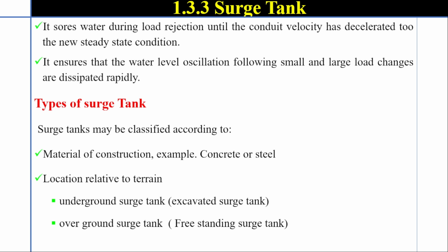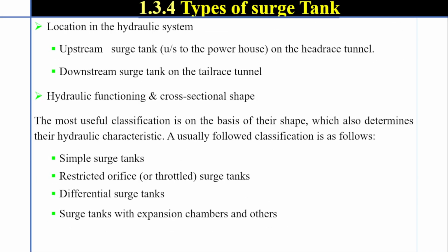Types of surge tank. Surge tanks may be classified according to material of construction, for example, concrete or steel. Location relative to terrain: underground surge tank, that means excavated surge tank, and overground surge tank or freestanding surge tank. Location in the hydraulic system: upstream surge tank, upstream of the powerhouse on the headrace tunnel, or downstream surge tank on the tailrace tunnel. Hydraulic functioning and cross-sectional shape: the most useful classification is on the basis of their shape, which also determines their hydraulic characteristics. Usually, the classification is as follows: simple surge tanks, restricted orifice surge tanks, differential surge tanks with expansion chambers, and others.